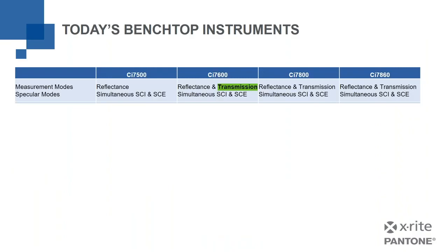So let's look at some specifications of these devices, and then after we go through these, we're going to overlay how the older instruments compare to them. First, in measurement modes and specular modes, as we go through this, across the top we have the 4 different devices, and then we list for each of them how they meet these various things. I've highlighted in green anytime we go from left to right where something has changed. For example, the 7500 is a reflectance only instrument. That's why it looked different. It doesn't have an opening to do transmission. It's for reflectance only. But the other 3, the 7600, 7800, 7860, all do transmission. All of them do simultaneous specular included and specular excluded. Those are really important, and if you are someone who needs to do both, that's a critical thing.